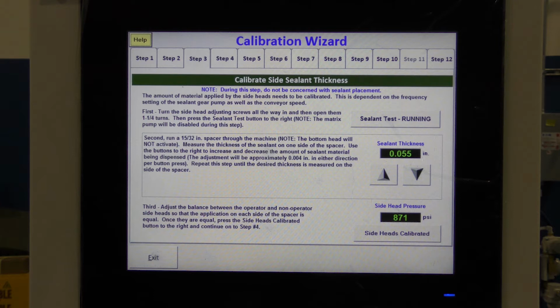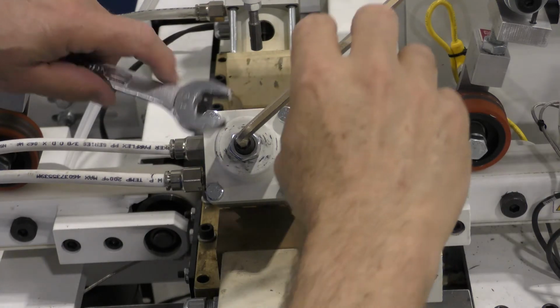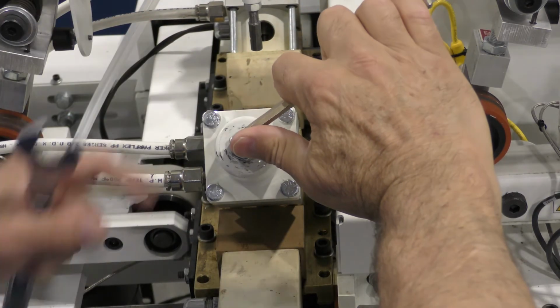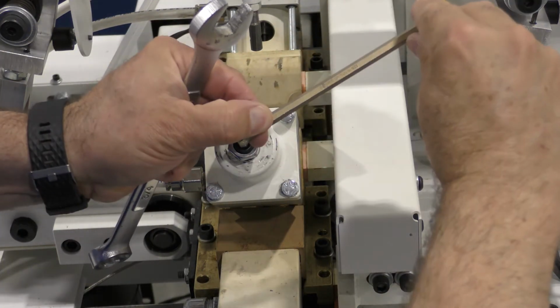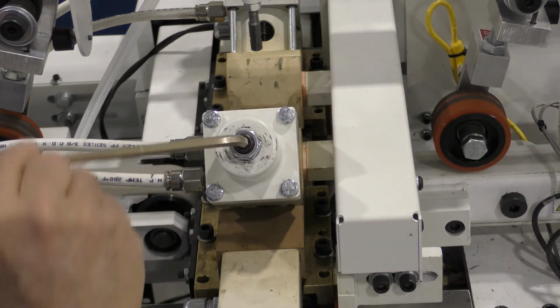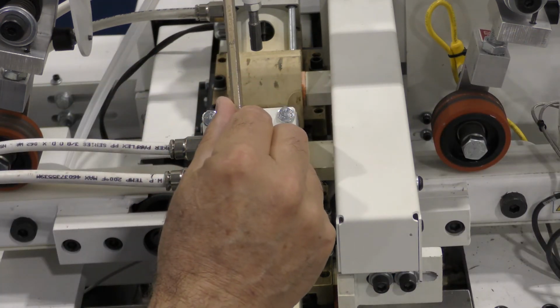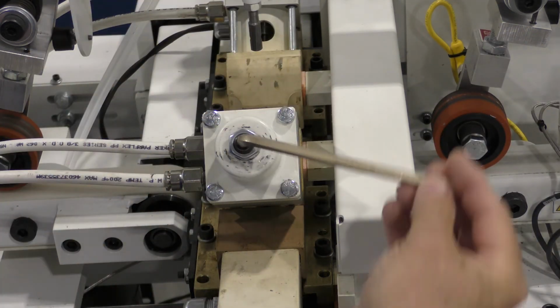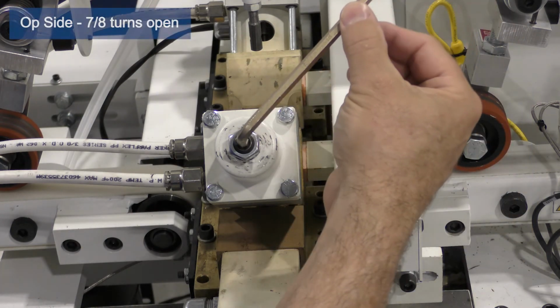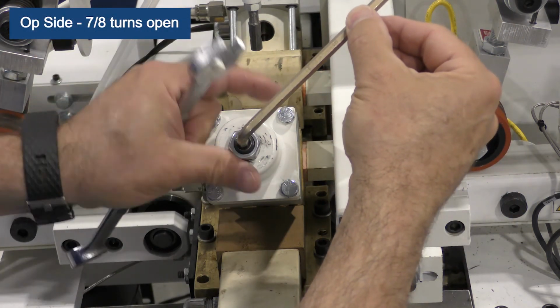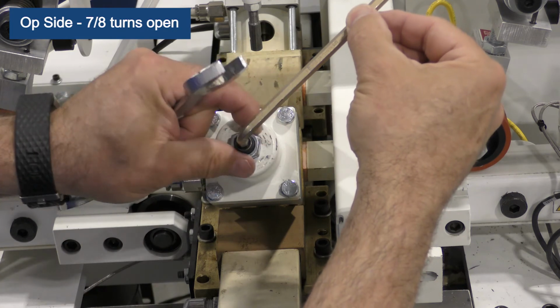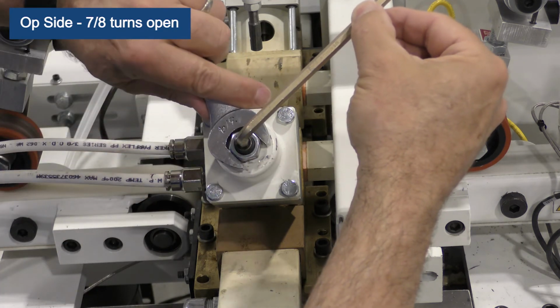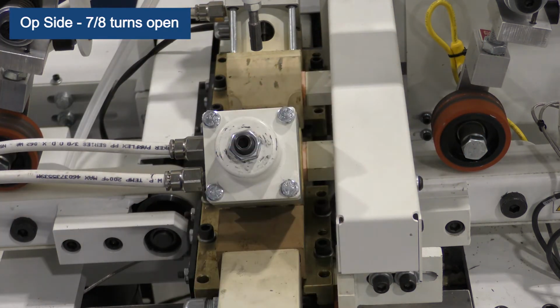I'm in a good place, but before continuing to step 4, document your current side head settings. When you have completed running these or any other calibration or setup procedures, it's highly recommended that you back up your parameters. Carefully loosen the jam nuts on each head and meticulously count the number of turns as they are closed. Open them back to exactly where they were, lock the jam nuts, and document the head settings.